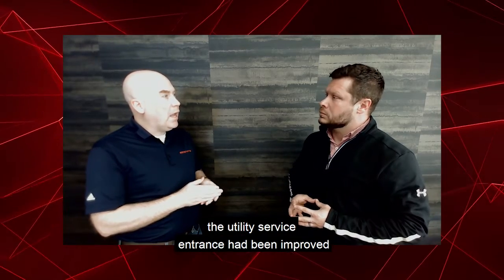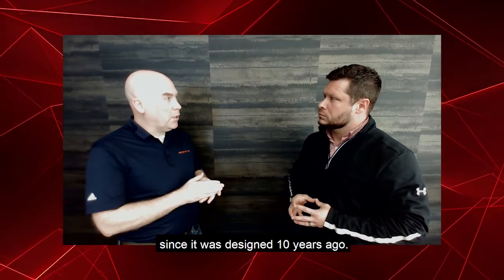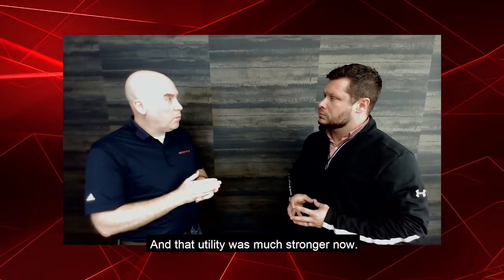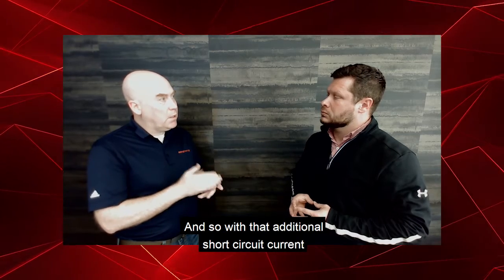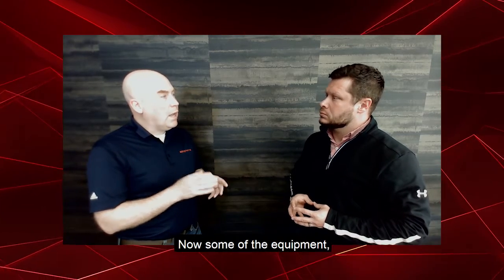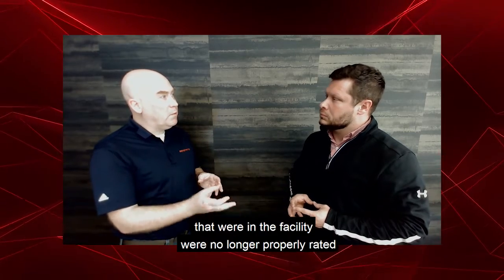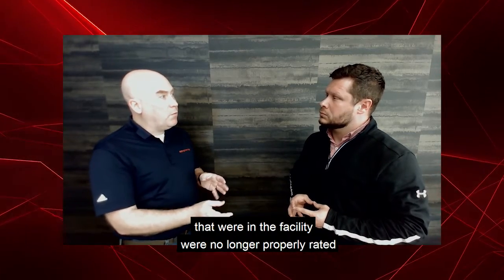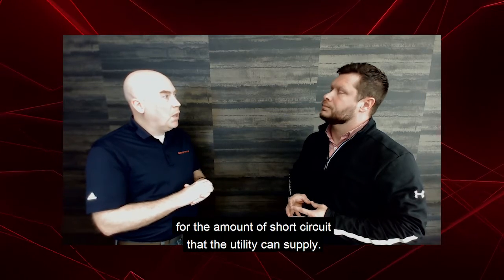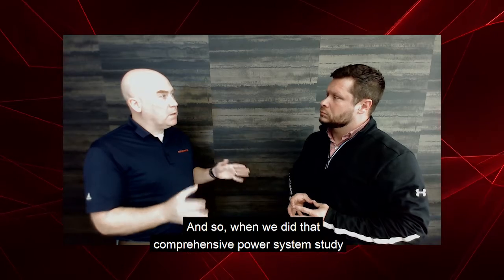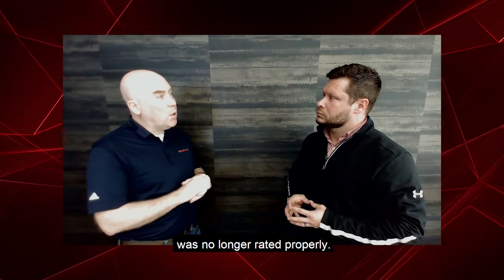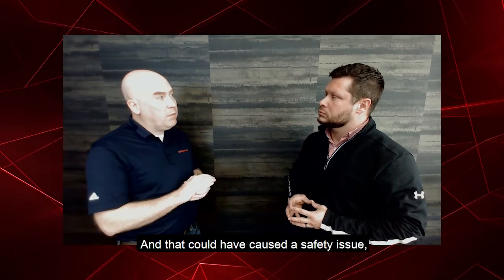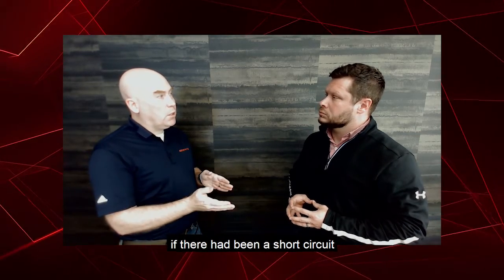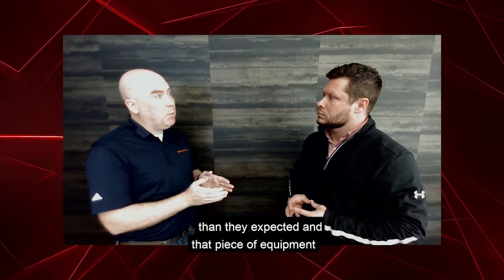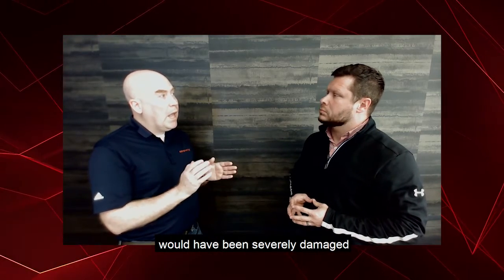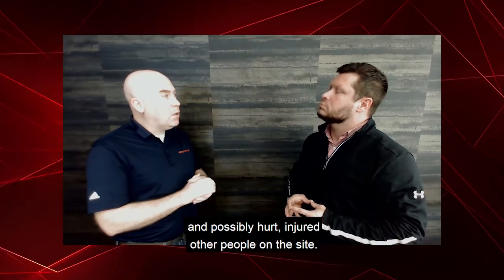That utility was much stronger now, and with that additional short circuit current supplied to the facility, some of the motor control centers in the facility were no longer properly rated for the amount of short circuit the utility could supply. When we did that comprehensive power system study, we found some of their equipment was no longer rated properly, which could have caused a safety issue. If down the road there had been a short circuit, the utility would have provided more energy than expected, and that piece of equipment would have been severely damaged and possibly injured other people on the site.